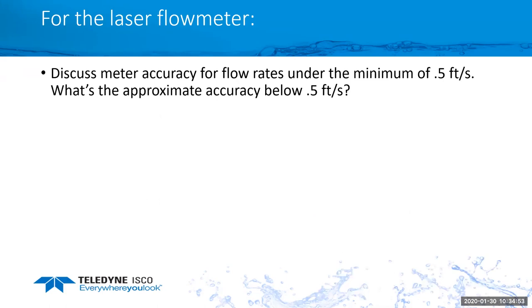Another question that came in is to discuss the accuracy of flow rates under the minimum 0.5 foot per second. As far as our testing and verifications, all have been done down to 0.5 foot per second. I do not have accuracy specs below that. However, we have had lots of applications that have read velocities slower than that, all the way down to 0.15 foot per second. As far as those readings, they look accurate. The customers I've dealt with have also thought that was an accurate reading. You'd have to do some independent testing with a bucket and stopwatch or something. If you have that slow of a velocity, you probably could do that.